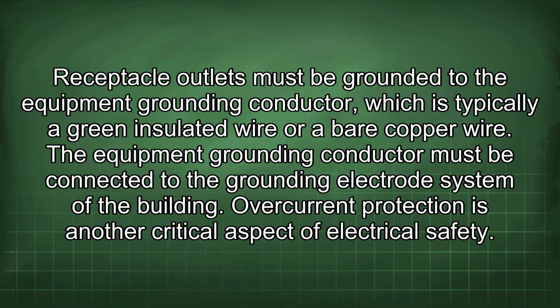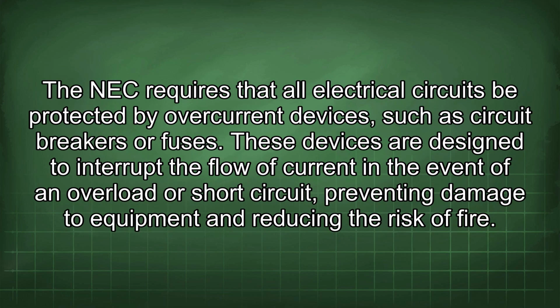Receptacle outlets must be grounded to the equipment grounding conductor, which is typically a green insulated wire or a bare copper wire. The equipment grounding conductor must be connected to the grounding electrode system of the building. Overcurrent protection is another critical aspect of electrical safety. The NEC requires that all electrical circuits be protected by overcurrent devices, such as circuit breakers or fuses. These devices are designed to interrupt the flow of current in the event of an overload or short circuit, preventing damage to equipment and reducing the risk of fire.